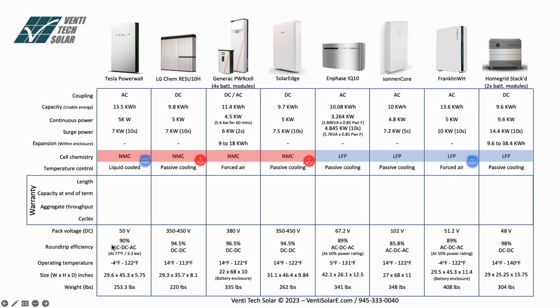Round trip efficiency, and in here you have to be careful because, for example, for the Tesla Powerwall, the efficiency is measured from AC to DC back to AC. So efficiency is compromised at 90%. 90% of the power that you use initially is what you're going to get at the end. In the LG Chem, you see higher efficiency, but they're only doing conversion from DC to DC, so low voltage DC to higher voltage DC. That's all they can do. But by the time you add the conversion from DC coupling over to the AC that the appliance will use, you have to add an inverter in there. You probably end up about the same range as the AC.